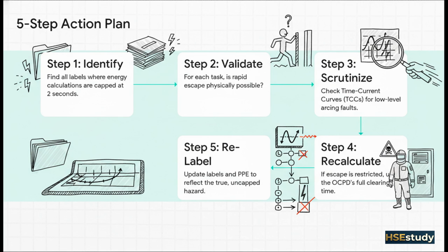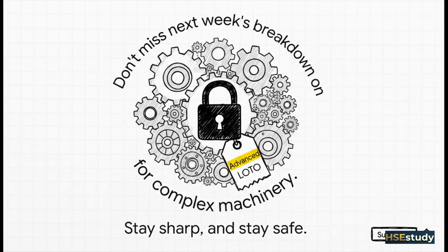Step 3. Scrutinize those time current curves. Look for those low-level arcing faults that fall into that long, slow-cook delay region. That's the heart of the problem. Step 4. If escape is not possible, you must recalculate using the full uncapped clearing time from the device. And finally, Step 5, the most important one. Relabel the equipment and update your PPE requirements and your procedures to reflect the true calculated hazard. Getting this level of detail right is absolutely critical. It's how we make sure our people go home at the end of the day.